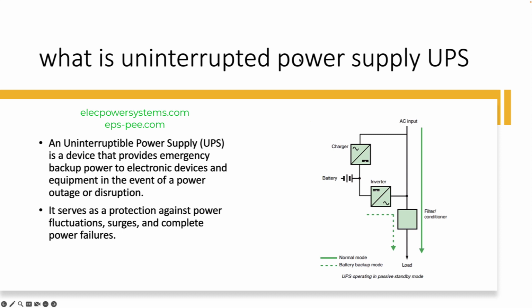When the main power supply is functioning normally, the UPS acts as a pass-through, supplying continuous power to the connected devices while simultaneously charging the batteries. In the event of a power outage or disturbance, the UPS immediately switches to battery power to ensure a seamless transition and uninterrupted operation of the connected devices. This allows users to save their work, safely shut down equipment, or continue working without any disruption.